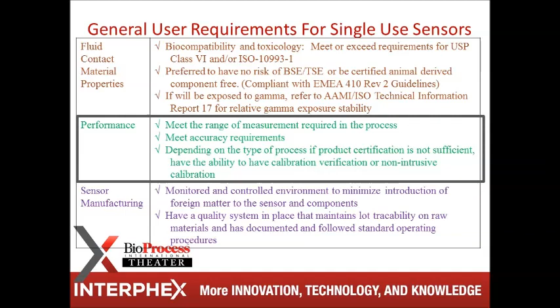And an important one is process compatibility. So you've got to make sure the materials are compatible with what they may see in a process. Usually preliminary screening for this is more just a chemical compatibility check. Later, if you're going to go towards implementation, you really need to do leachables and extractables. And you have to make sure that physically the sensor will withstand the process parameters. So not that it may have to measure at all these parameters, but you want to make sure it's not going to fail or crack or anything like that in case there's accidental exposure. And you also want to have a clean integration so it doesn't interfere with any of your process operations.